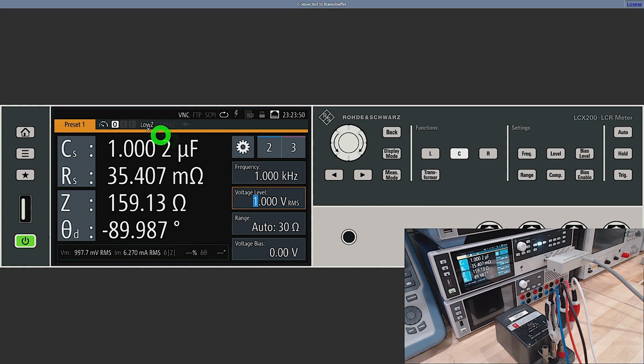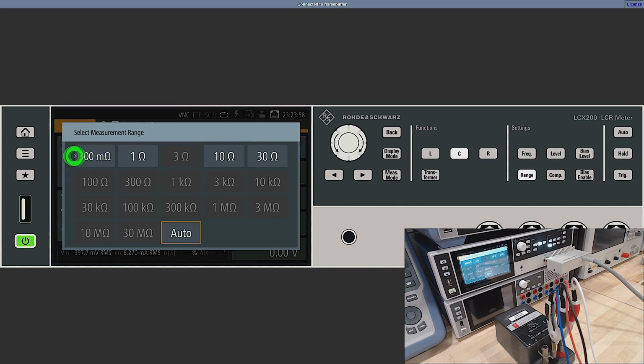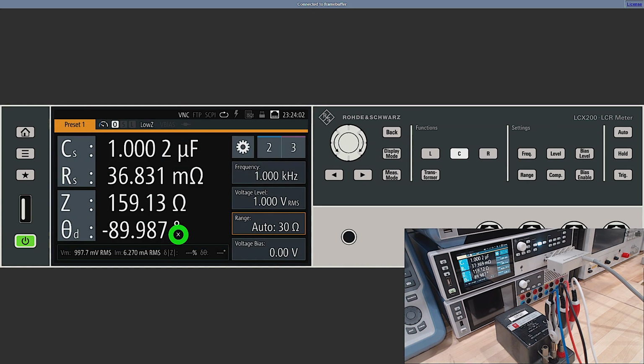But you can see that when the source impedance is small, the VM measurement internally and the voltage level applied are much closer together. Now, if you look at the range here, the range has shifted. Now you have these ranges at the top that you can use. So I think some clarification is required, especially on how the auto ranging and the LowZ mode and regular mode interact with each other, and sometimes it can get confusing.